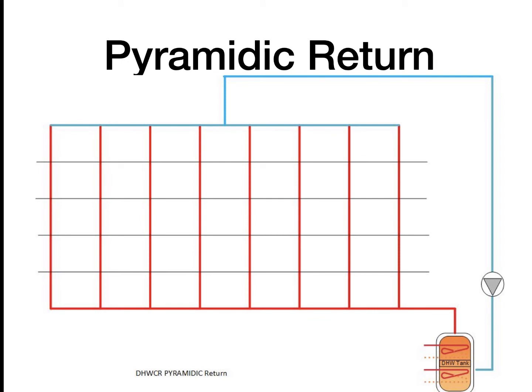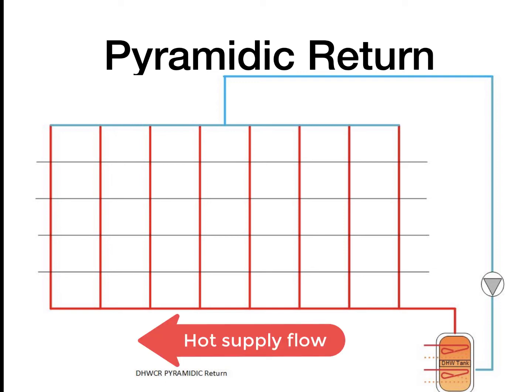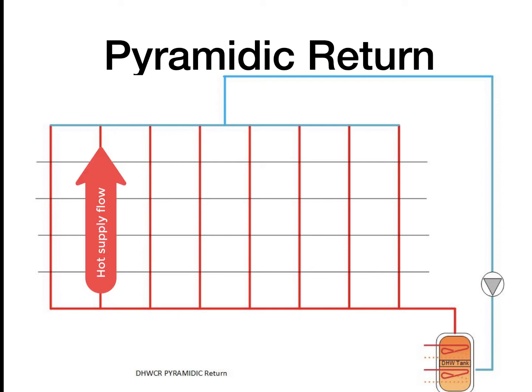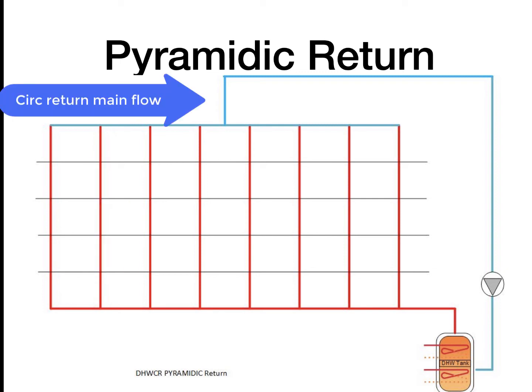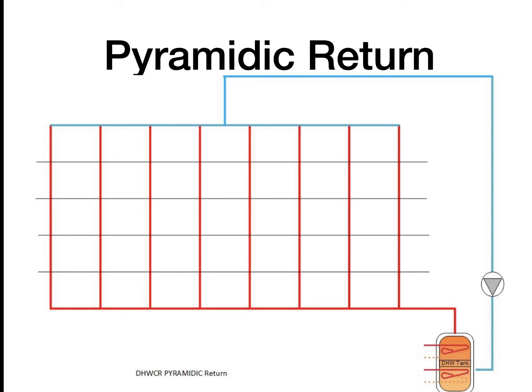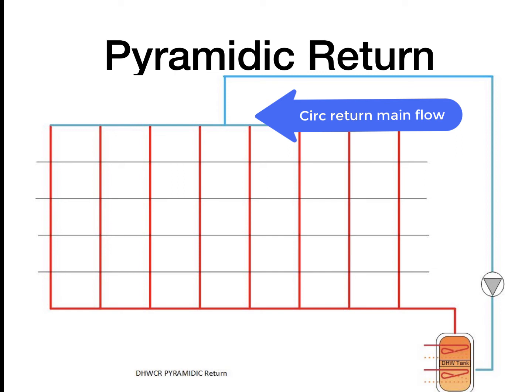This is a pyramidic return system. Essentially, the hot water supply main runs horizontally, and then all of the vertical branches would be the risers that would go up through the apartment complexes themselves, and then they would hit a header at the top, which would be the circulation return header. But on the left-hand side, it flows from left to right to the center, and the right-hand side would flow from right to left to the center.